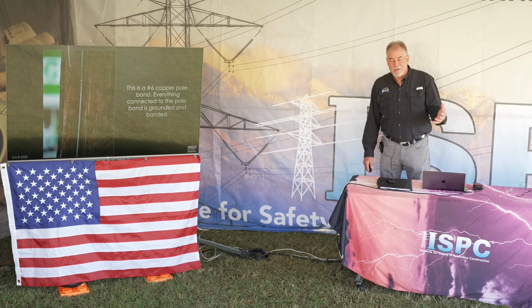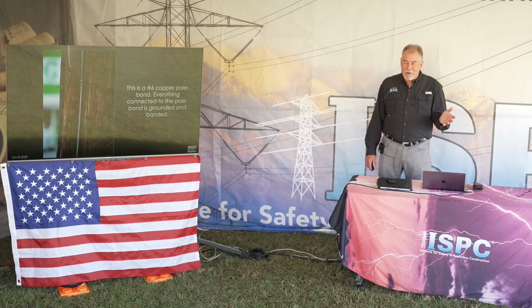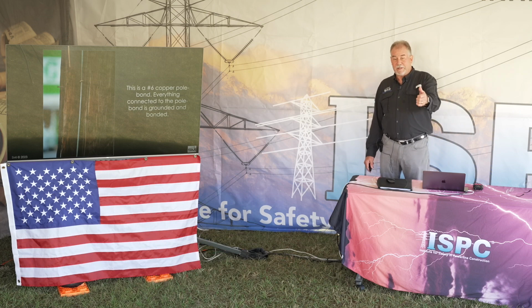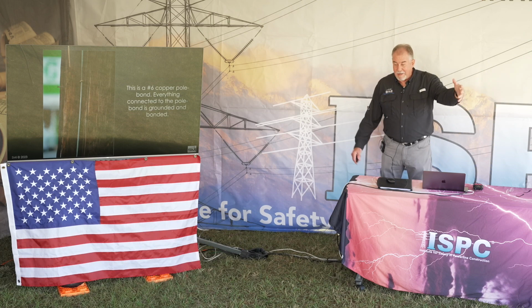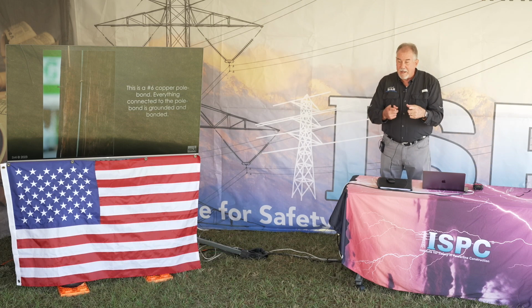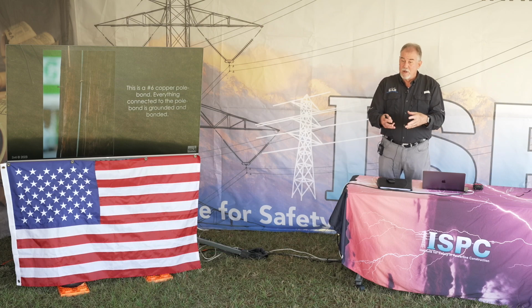There's always amperage on these grounds. Now, is it a hazard? No, it's perfectly safe, everything's bonded and grounded. But if I was holding this ground wire and a truck down the road hit a guy wire and made the energized conductors touch that neutral, it's going to energize this too. Now how many volts, we don't know, every scenario is a little different. But the point is, we don't want to spend a whole lot of time in contact with things like this.